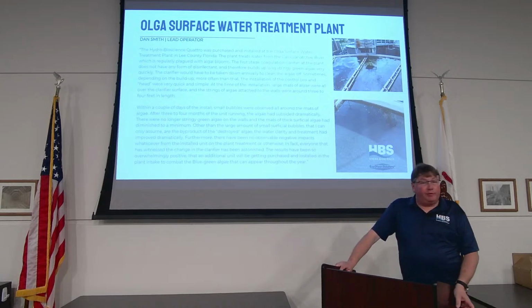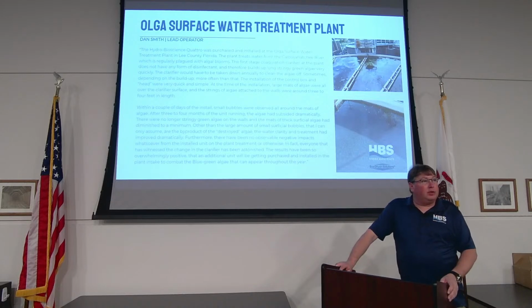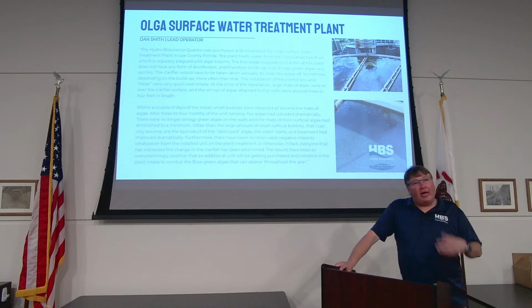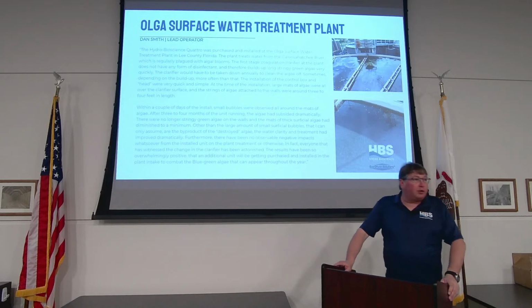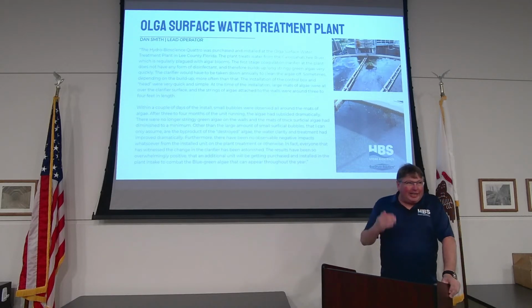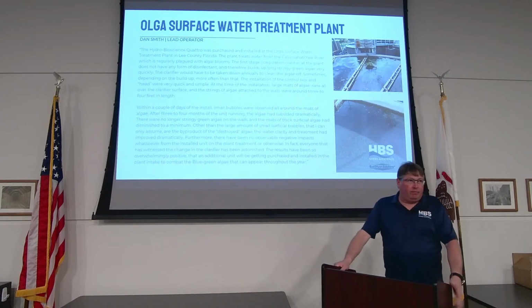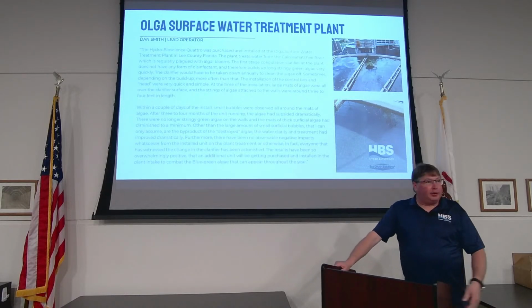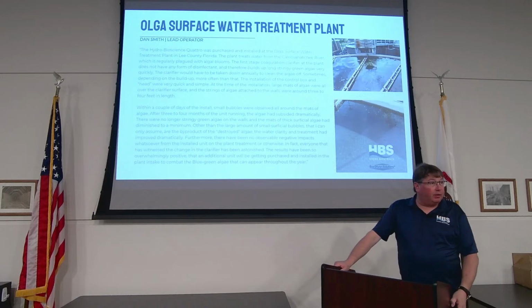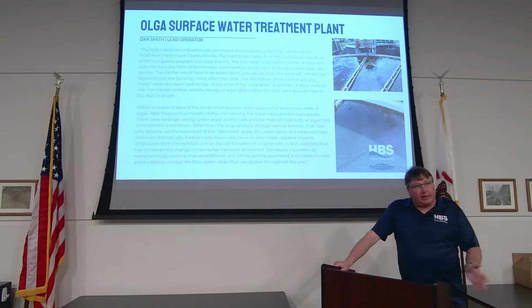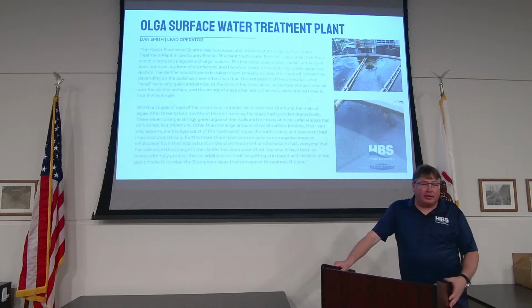When you first do an install, I say check it after 2 weeks and judge it from there. As ultrasound starts to work, your cleaning times will spread out much more. As you're killing off the algae and moving the biofilms out of the way, you will reduce the number of times you have to clean it. But I say 2 weeks in wastewater. I say once a month in drinking water reservoirs, holding tanks, things like that.